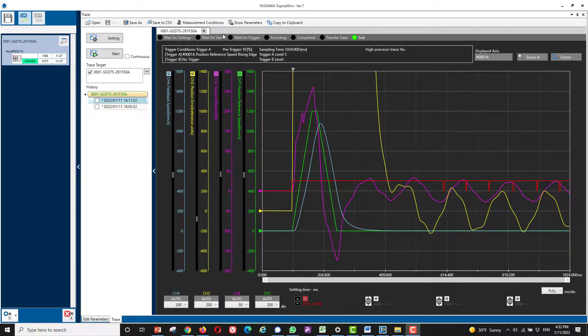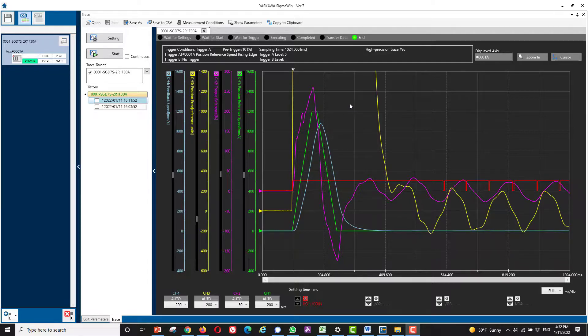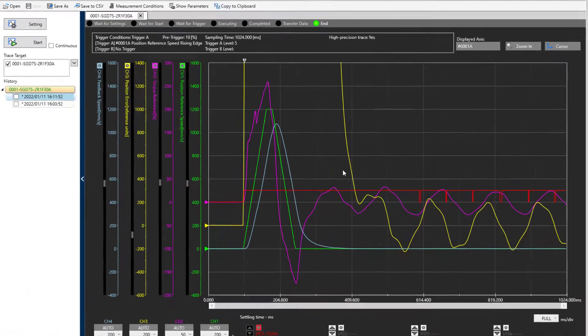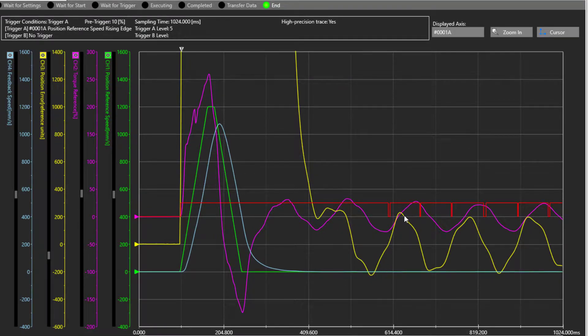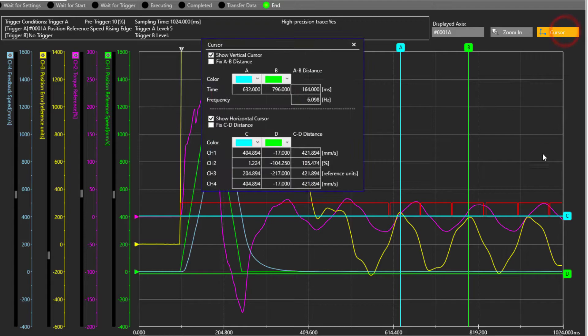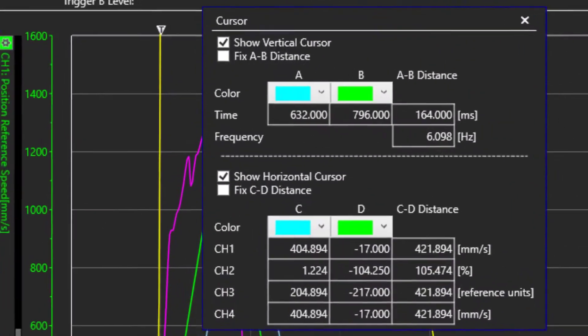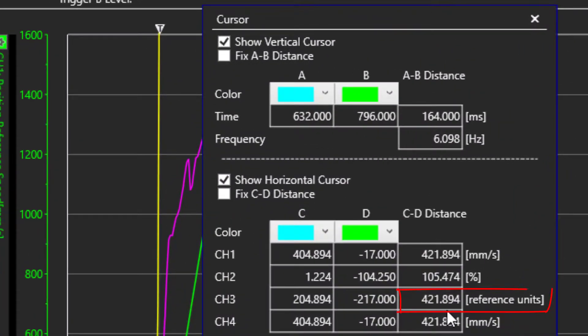A trace shows that this vibration is easily detected by the encoder as position error with an amplitude of about 420 reference units, which is about 33 microns.